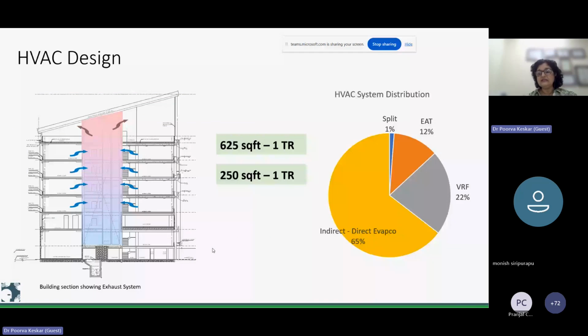So in the HVAC system, direct evaporative cooling was used for 65% of the space, VRF was used for 22% of the space, and the earth air tunnel was used to cool 12% of the space. Typically 1 TR would generally be used to cool 250 square feet, but here we saw that 1 TR was used to cool 625 square feet.